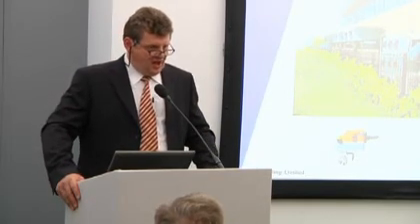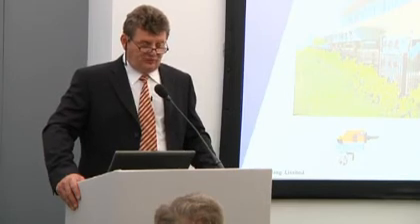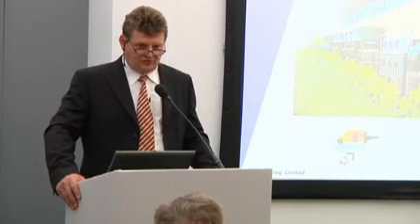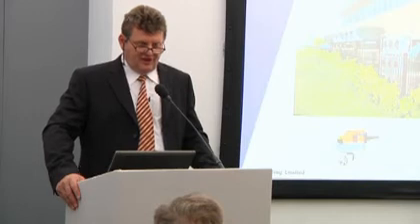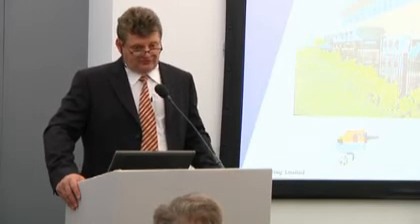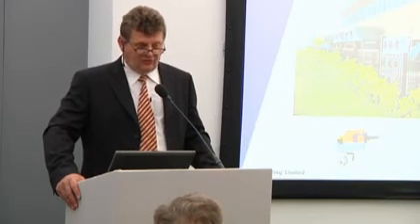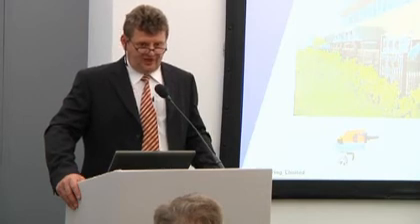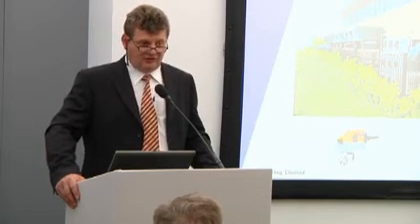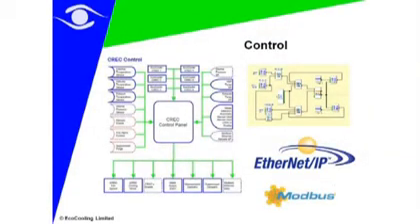If something fails that we haven't been able to pick up automatically or electronically, the pressure will drop, the system will see the pressure drop, and all the other cooling systems and their fans will ramp up their speed accordingly and raise an alarm condition. All this is linked together through what we call our control panel.